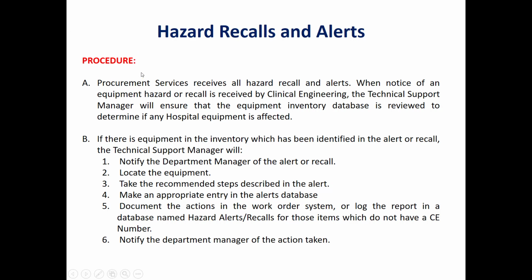Such a procedure is separated into two steps. The first step: the hazard recalls and alerts are received by the procurement services, which send a notification or a notice to the clinical engineering department.